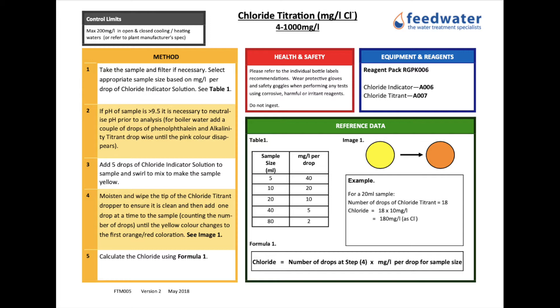If the pH of the sample is greater than 9.5 it is necessary to neutralise pH prior to analysis. For boiler waters add a few drops of phenolphthalein and alkalinity titrant drop wise until the pink colour disappears.